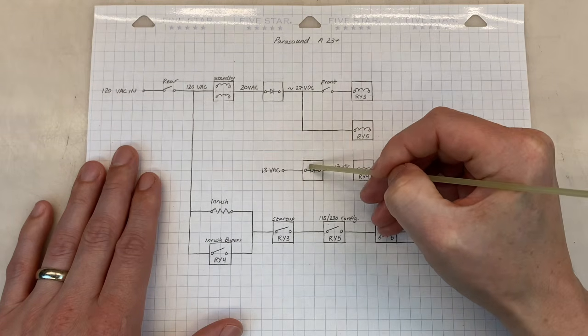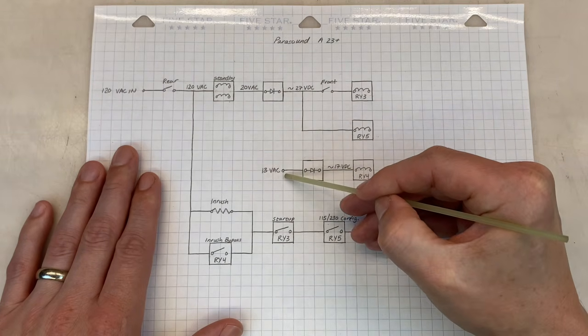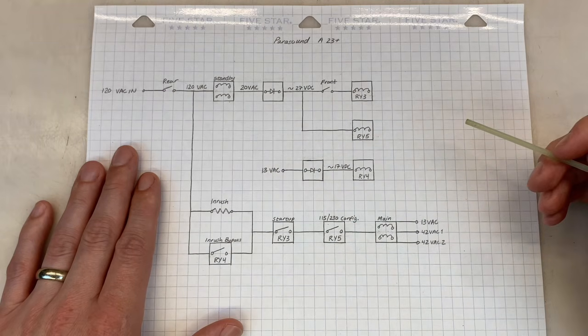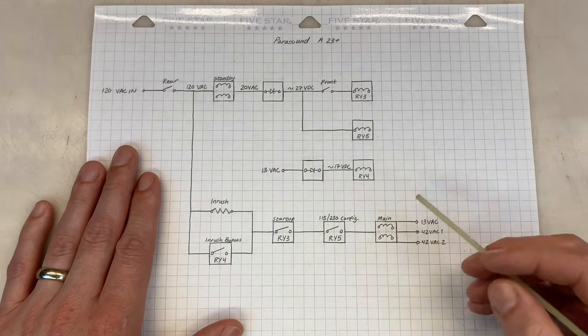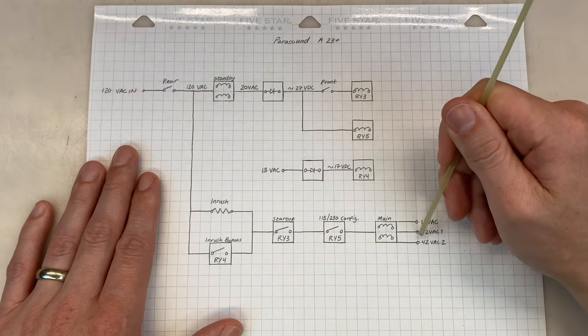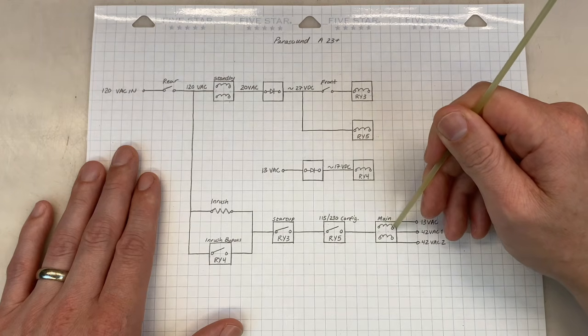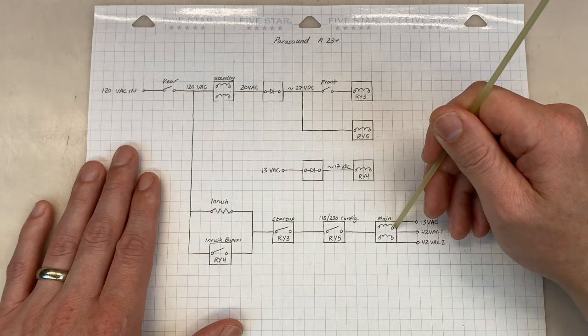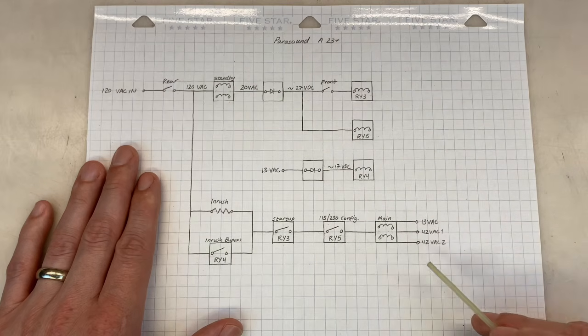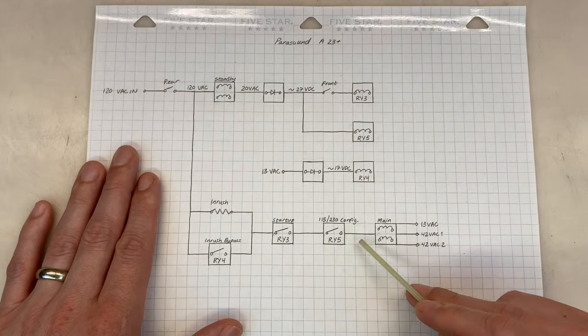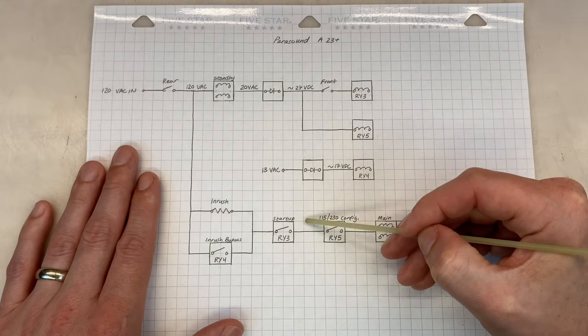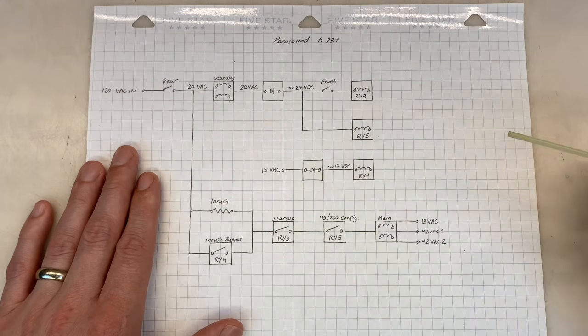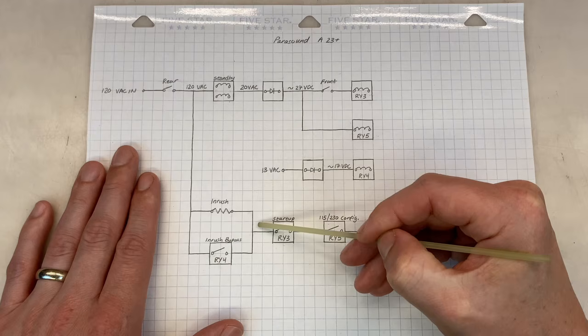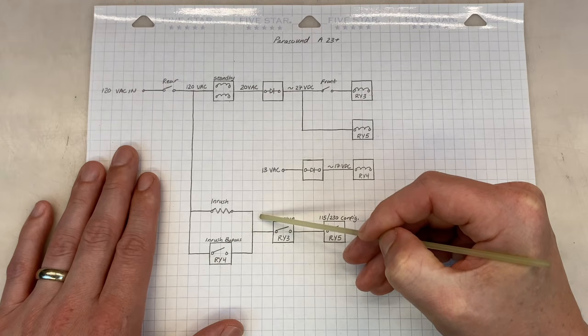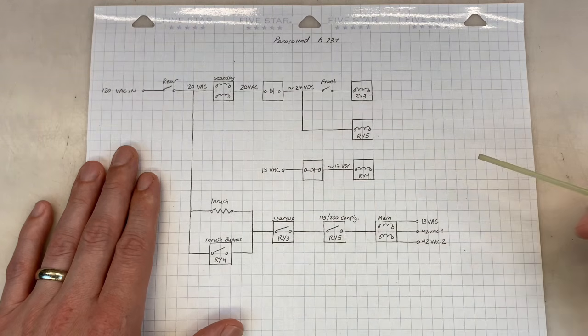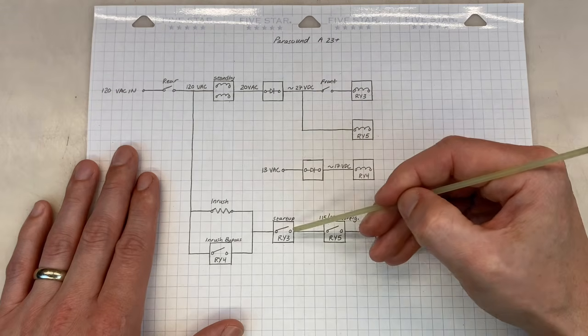I then measured the input to this bridge rectifier, looking for something like 13 volts AC, and saw nothing there as well. So from there, I went to the main transformer. I looked for these 13 volts, 42 volts, and 42 volts directly off the secondary of the main transformer and saw absolutely nothing. I then measured the input to the transformer right here, saw nothing. I then measured the input to relay RY5 here and saw nothing. And finally, when I measured the input to relay RY3 right here, I did see 120 volts of AC, which led me to believe that one or both of the contacts of RY3 were bad.